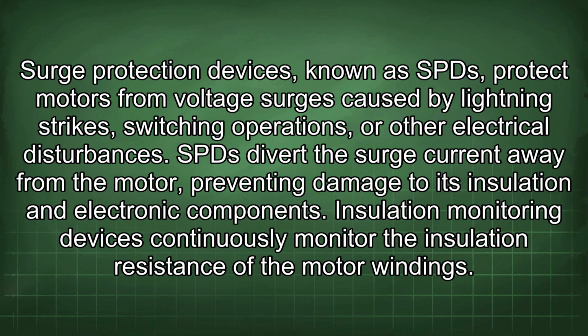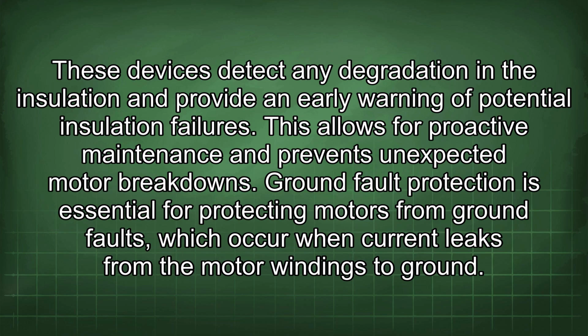Insulation monitoring devices continuously monitor the insulation resistance of the motor windings. These devices detect any degradation in the insulation and provide an early warning of potential insulation failures. This allows for proactive maintenance and prevents unexpected motor breakdowns.